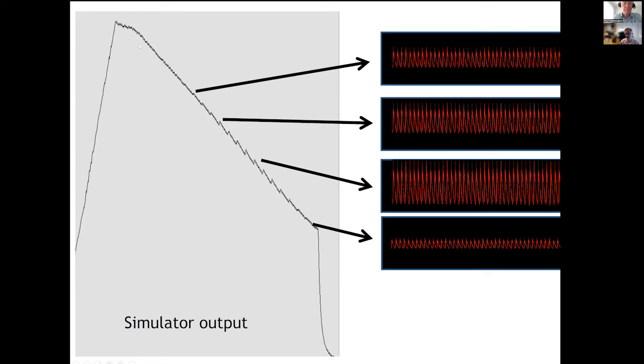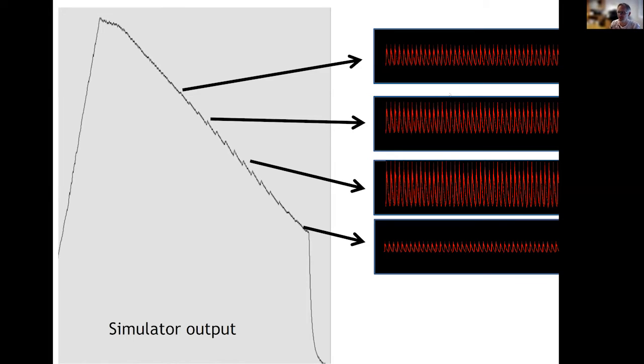This is another picture of deflating pressure with all these pressure pulses, and I put some pictures of the pressure pulses here. So basically, the simulator generates the proper pulses according to the pressure, meaning the amplitude of the generated pressure pulses depends on the pressure in the cuff. Firstly, the pressure pulses are small, as you can see here, and then they get larger, and then they get smaller again.